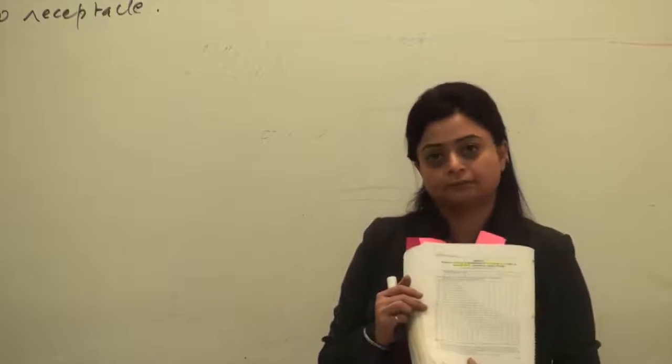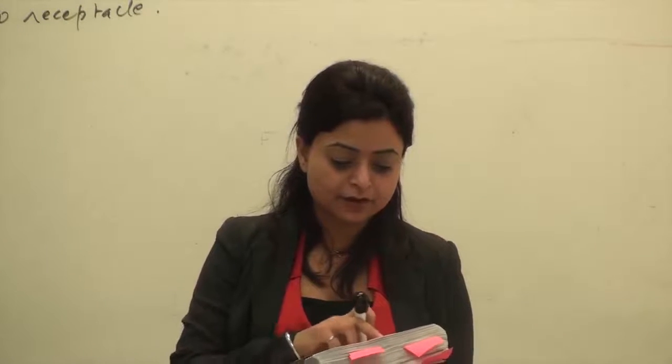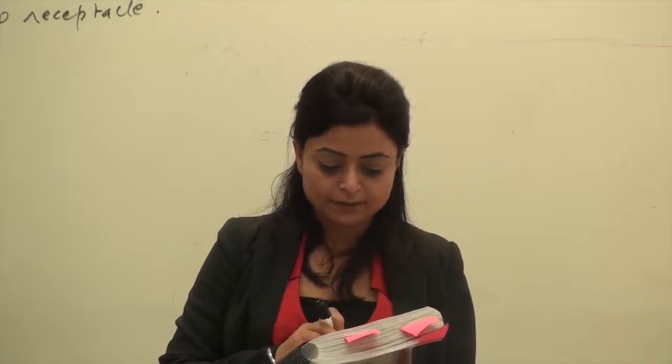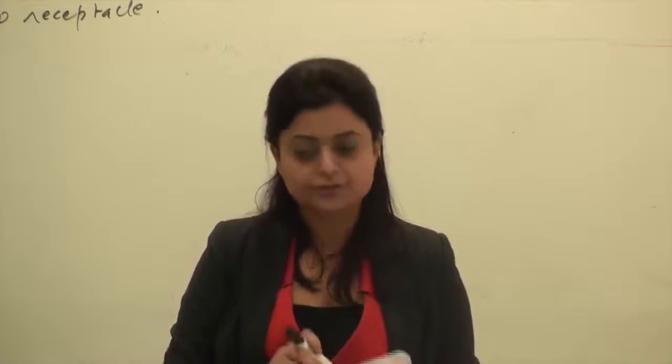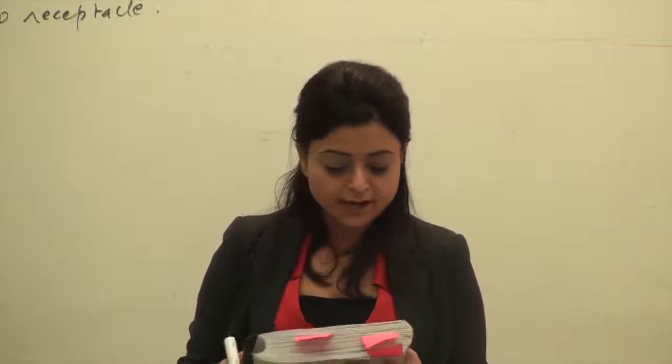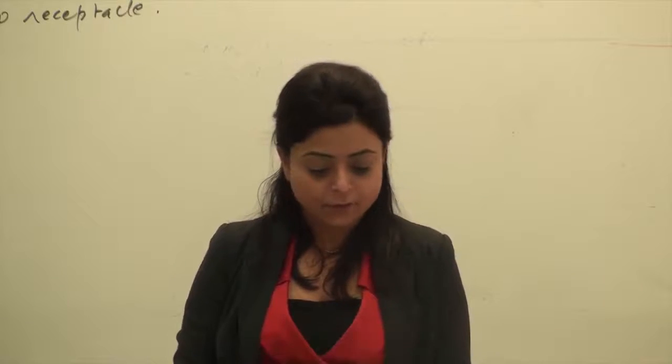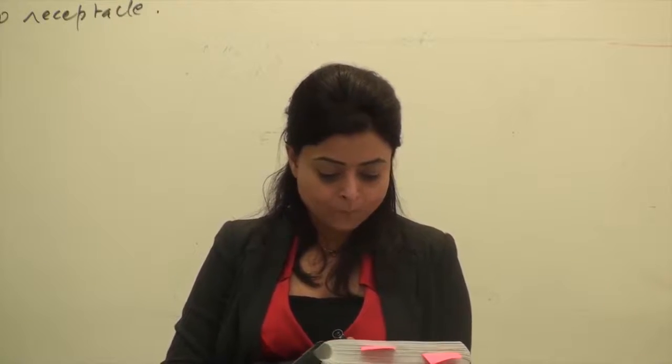Okay? So Satinder, if I had number 10 conductor here and 10 amp service, how much length of conductor is allowed? Number 10 and 10 amps. So 10 amps, you will go to a row of 10 amps and a column of number 10, I get 15.5 meters. Good job. Jaswinder, if I had 40 amp service and number 4.